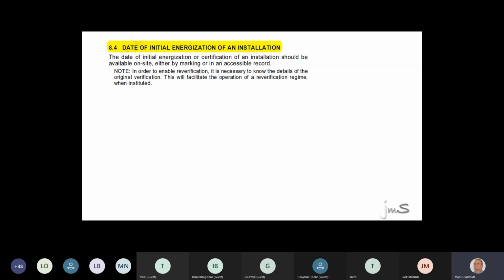You walk around the house, you look in the ceiling, and you look at the top of cable. Firstly, could you remember years ago, no, this is before your time, you used to have a neutral earth bar with no link. It was just one bar. That tells me it's a 1960 type of house. In 1992, they decided to take the atom and they split it. Oh, sorry, the neutral bar and they split it. Who split the atom? Mr. Rutherford. Right, who split the neutral earth bar? Well, the EWRB decided. So if I give you a neutral bar, earth bar, and a split, you'll say, oh, well, that could be after 1992.